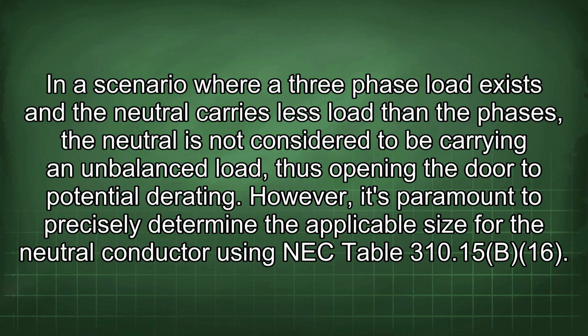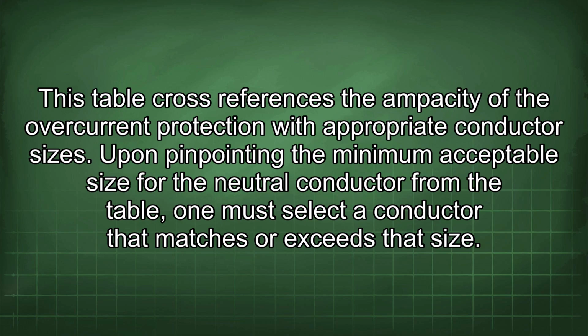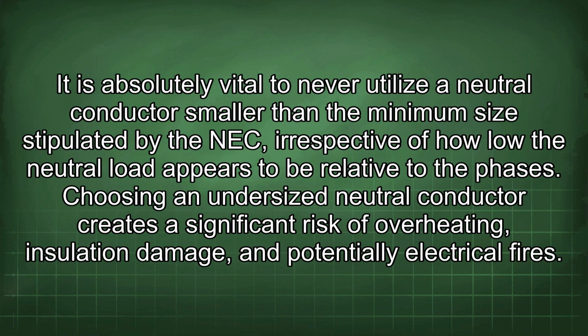However, it's paramount to precisely determine the applicable size for the neutral conductor using NEC Table 310.15(B)(16). This table cross-references the ampacity of the overcurrent protection with appropriate conductor sizes. Upon pinpointing the minimum acceptable size for the neutral conductor from the table, one must select a conductor that matches or exceeds that size. It is absolutely vital to never utilize a neutral conductor smaller than the minimum size stipulated by the NEC, irrespective of how low the neutral load appears to be relative to the phases.